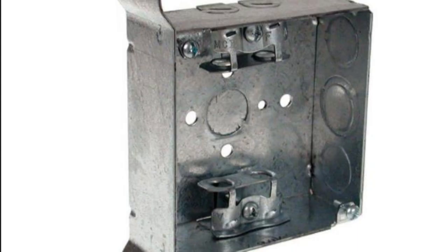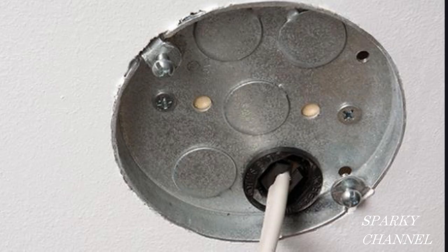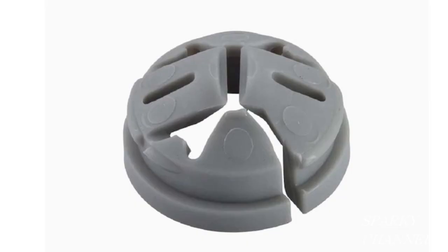Here's some clamps that are interior clamps, and I think we would all agree they are interior clamps and should be included in box fill calculations. Here's a little clamp that I feel would be an exterior clamp because most of it is actually outside of the box. This one could be a little controversial though.